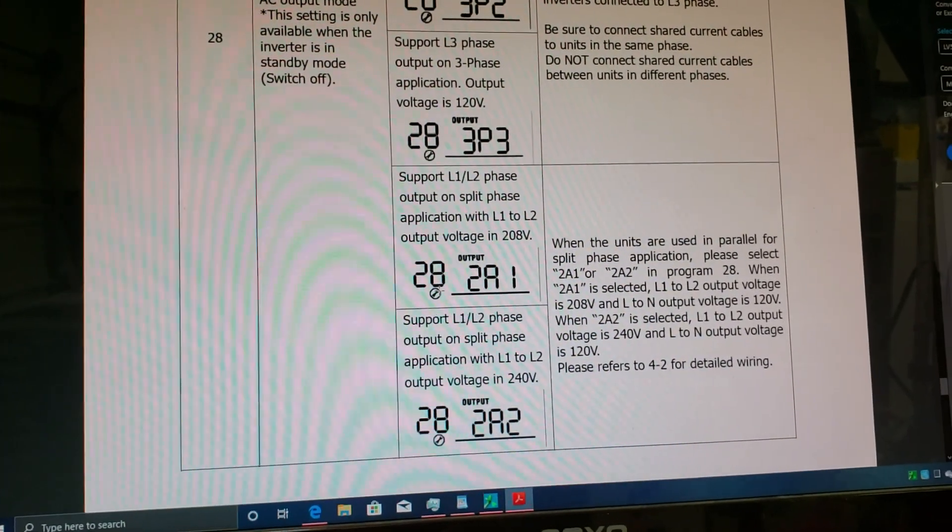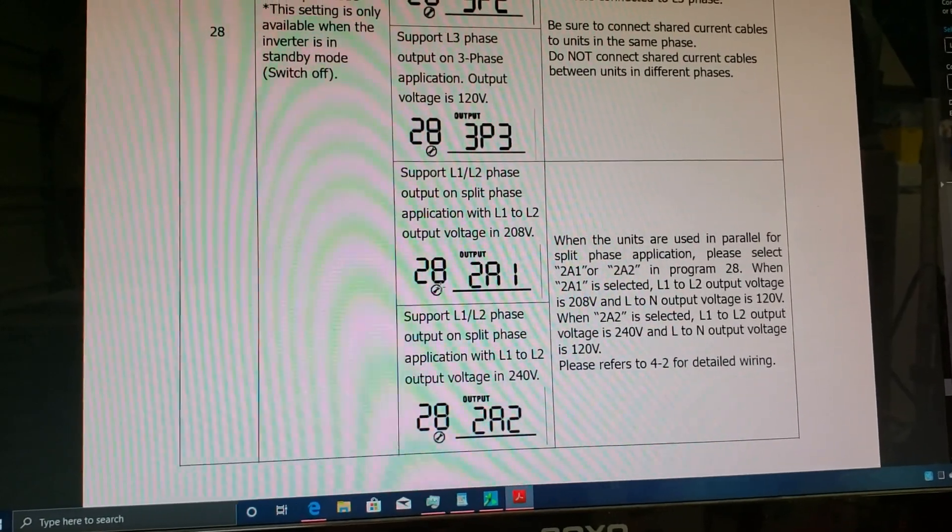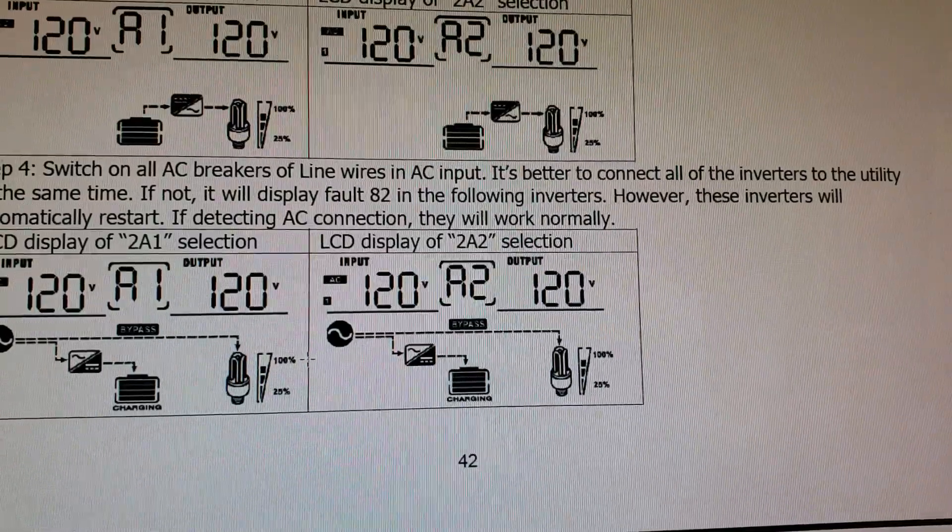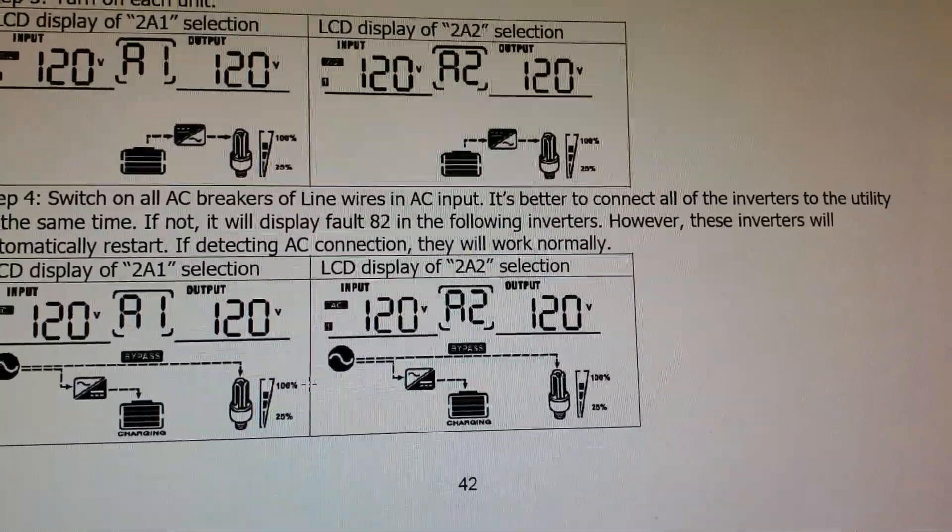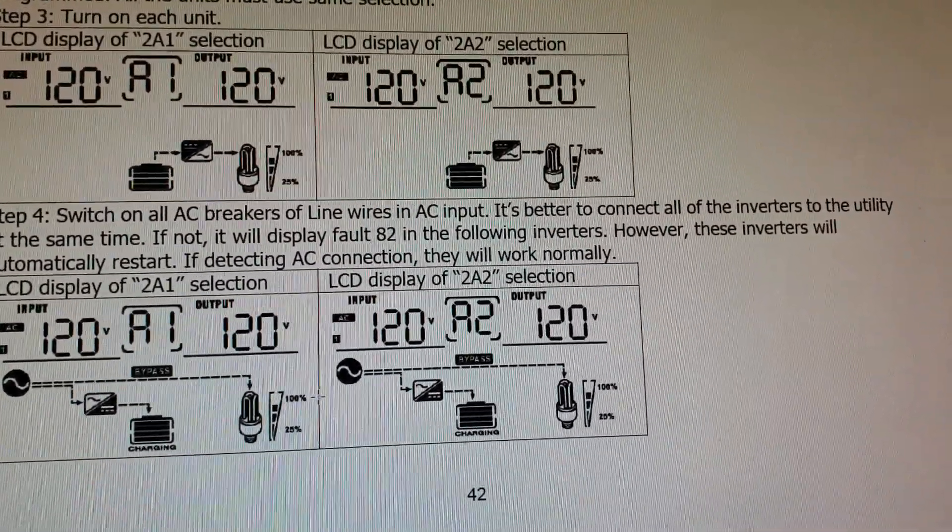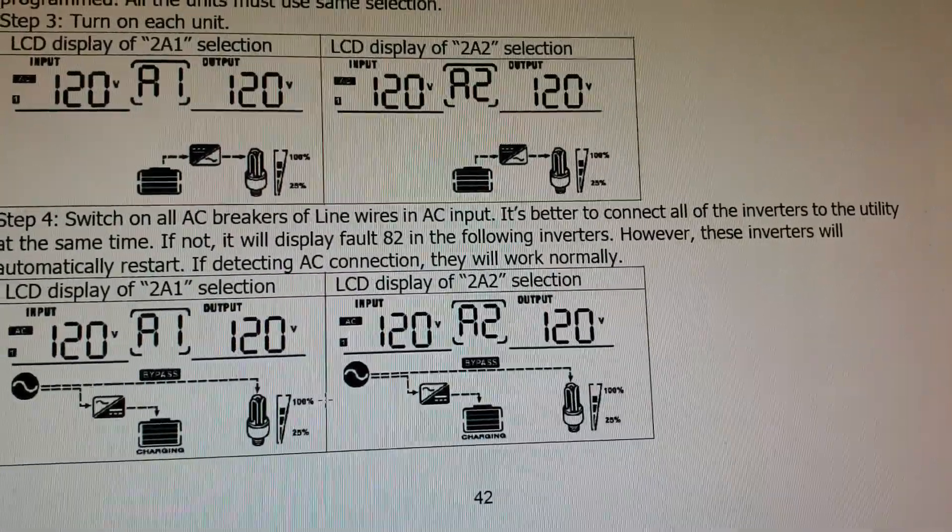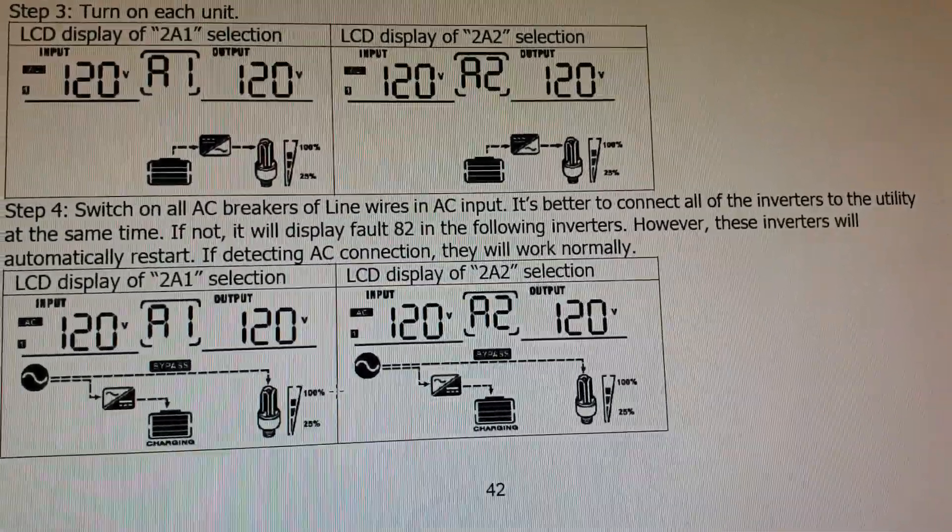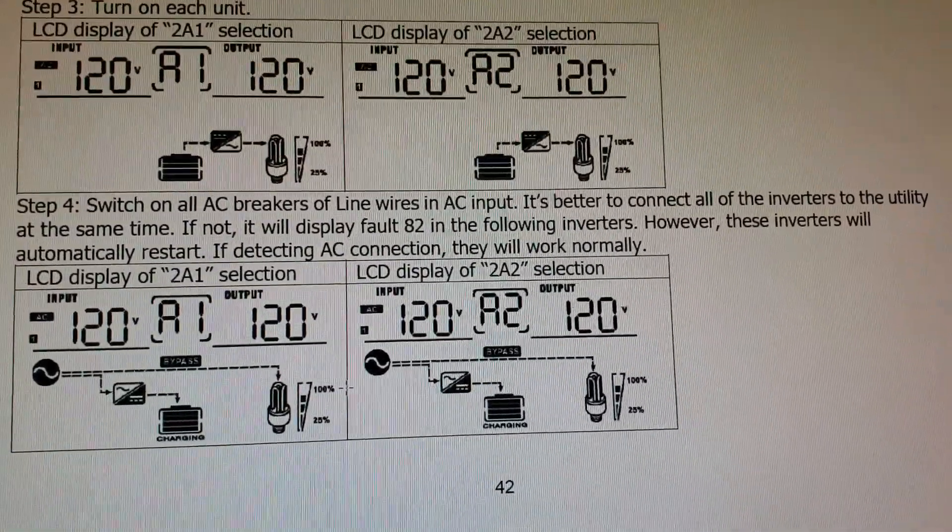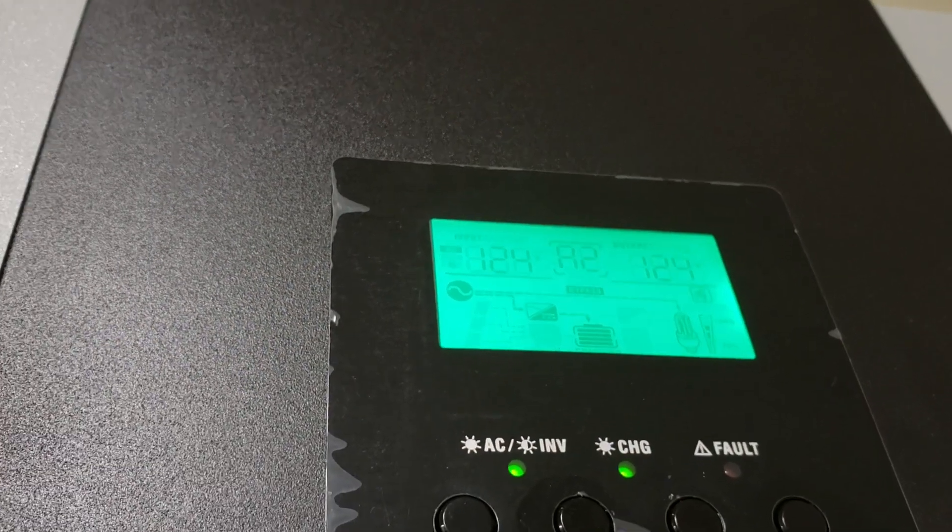After finishing that, I immediately turned on both switches on both units at the same time and let them boot up. After finishing the boot process, the menu on the LCD changed to what you see right now. It has AC input of 120 and 120, exactly as it is on this picture right now. Here it is how it looks like right now when you have it set up properly to work in parallel mode split phase setup on these units.